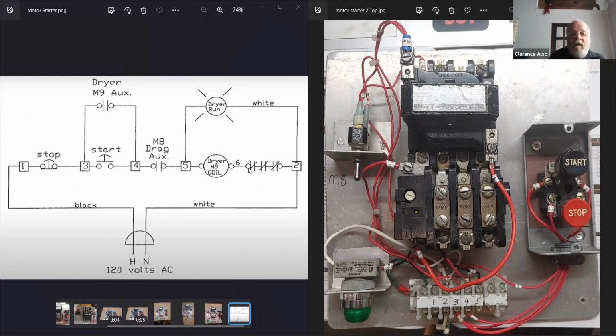Now you tell me you want to put the probe there at the 6 side of the overload. That means with that other probe you've got, 6 is right here—there's a little screw there. Then with your fingers, you're going to pick up the end of the probe and hold it on there.